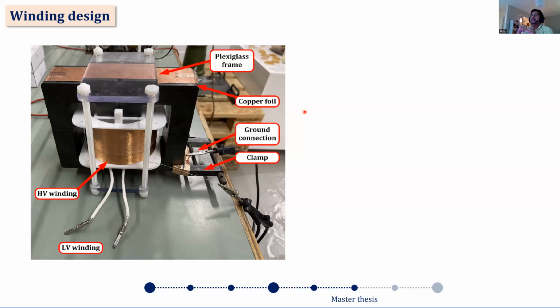We had the high voltage winding on top, and you can see a lot of grease applied on it, and the form factor is extremely small. The reason was that we were limited in the cores we could purchase. Also, if you have a higher area, the flux linkage will be poor, causing lower voltage regulation. So it is a very tightly constrained design. If you move in any direction, there's always something you're losing out on.